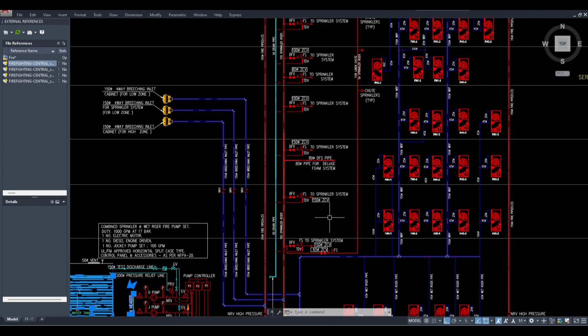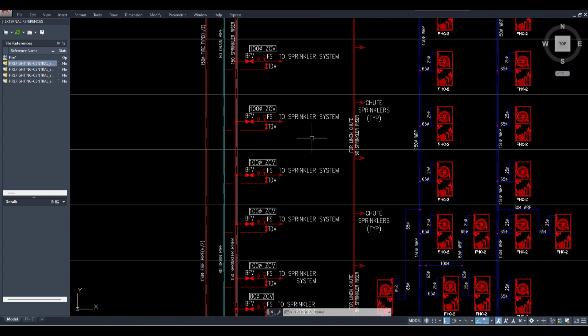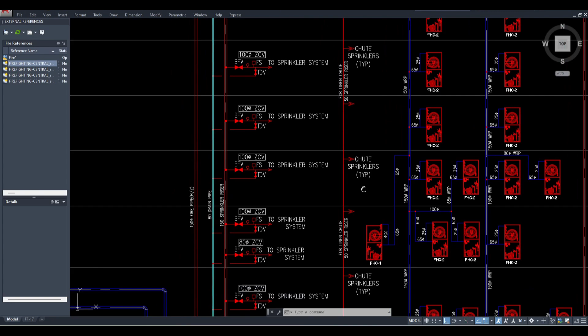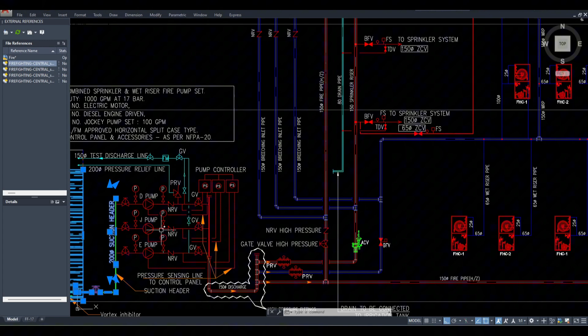fulfilled. But suppose an actual fire is happening and somewhere the sprinklers are activating and continuously discharging water, or your fire hose reel is working, someone is operating it. So in that case also, it is continuously taking water, and this pump is not a very powerful pump, so as I told you, it delivers less water. Okay, so it has a certain capacity, and only on that it can deliver.